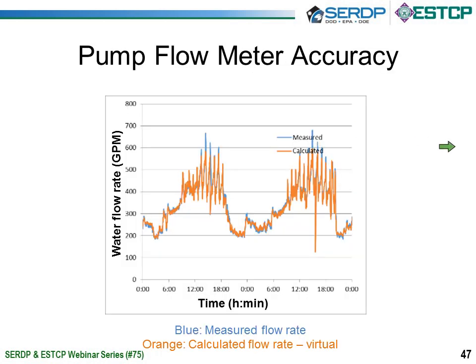To give you an idea of the accuracy on the water side at least, we have a plot here of the water flow rate versus time for a period of 2 days. The blue line represents the measured values, and this is using the ultrasonic flow meter. The calculated values are the virtual values, and you can see that there's excellent agreement except for the peak values around the middle of each day of these plots. Overall, this is excellent agreement.